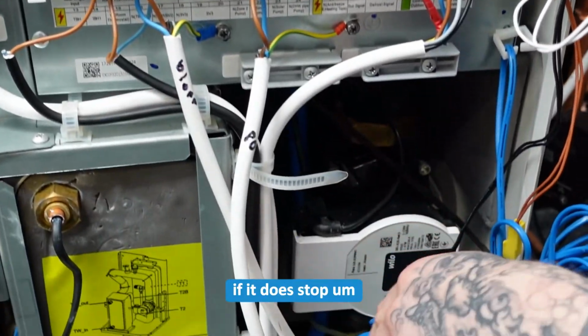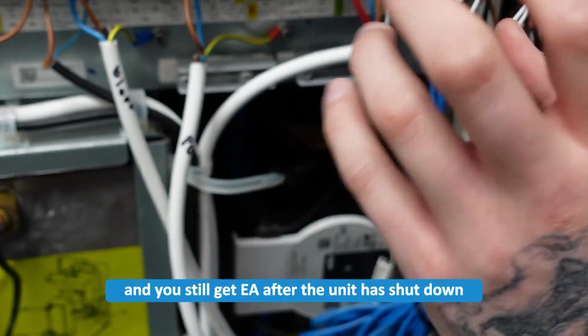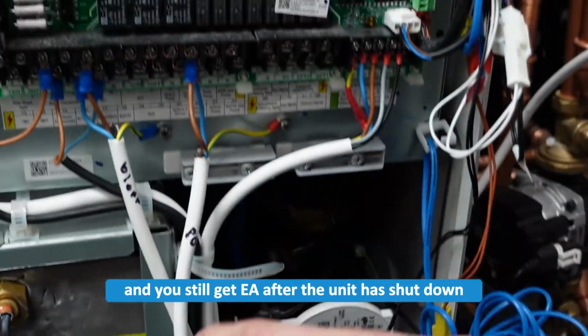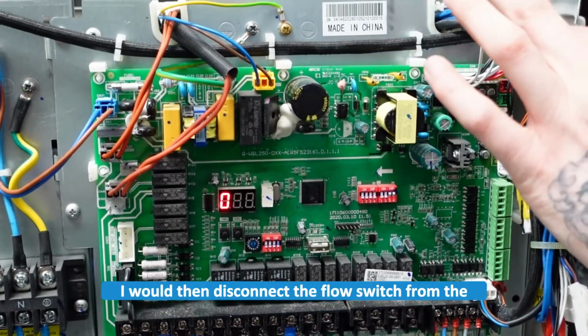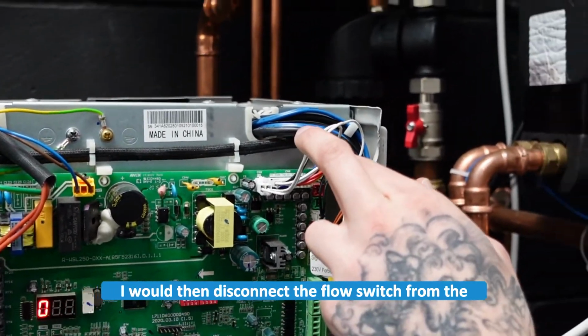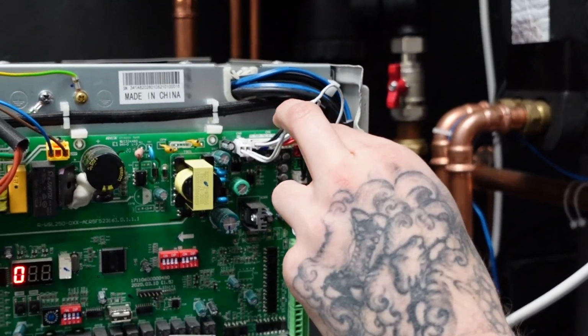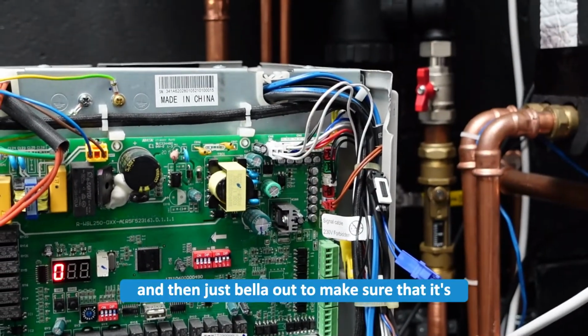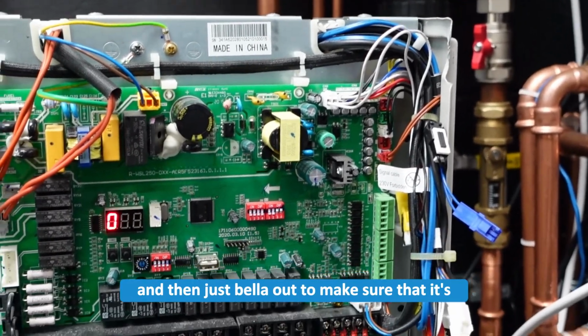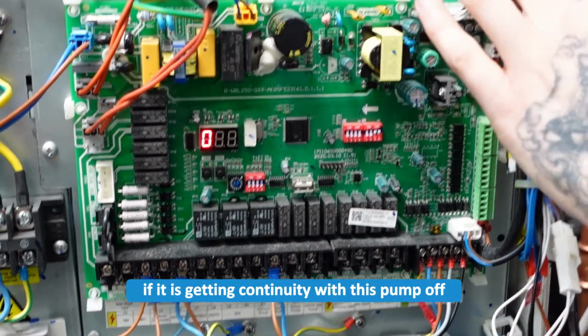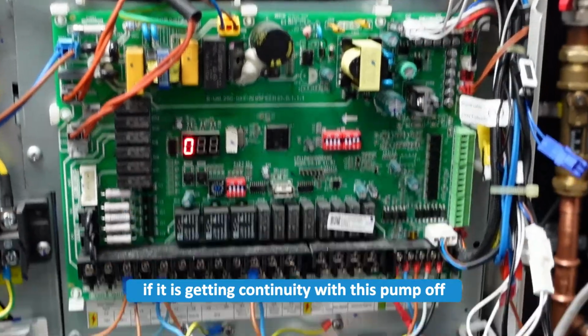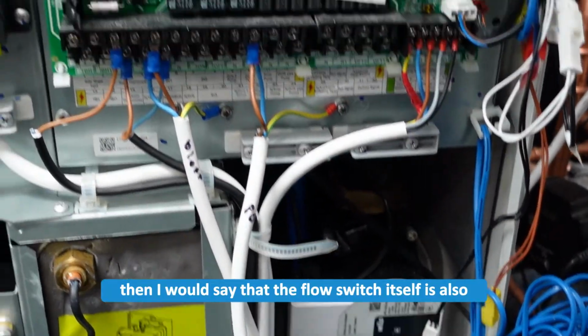If it does stop, and you still get E8 after the unit has shut down, I would then disconnect the flow switch from the PCB once again, and then just bell it out to make sure that it's getting continuity. If it is getting continuity with this pump off, then I would say that the flow switch itself is also probably knackered.